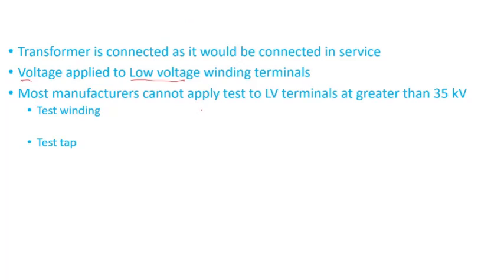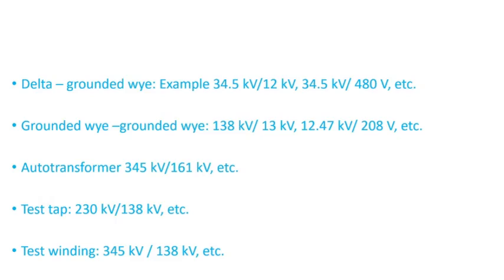Most manufacturers cannot apply the test to the low voltage terminals if they are greater than 35 kV. In that case, some manufacturers might add another winding just for testing purposes, and it will be permanent — it won't be removed after the test. Other manufacturers might put a test tap within the low voltage windings so they can apply the voltage during the induced test.